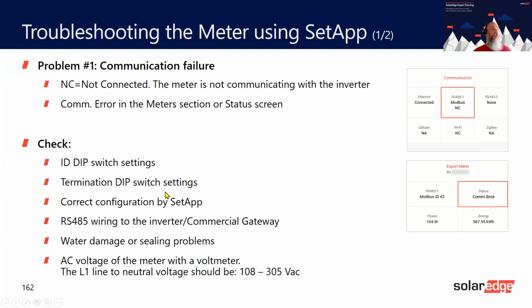Then check the dip switches on the setup. Make sure you put it as number 2. Then make sure you've configured it correctly, that you've got it set for import, export, production, or consumption. Check the wiring to the inverter, the gateway, to make sure that you do have the BAG and you have got the right color in B, the right color in A, and the right color in G.